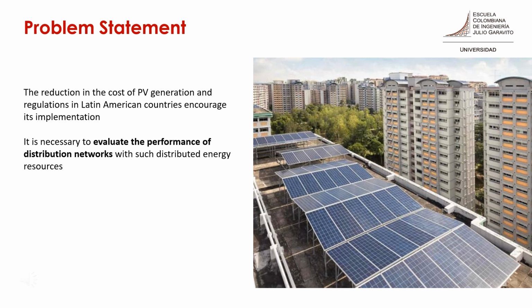Given the stochastic nature of PV generation and the lack of control over its location, the operation of distribution systems becomes more complex. In this way, if the network operator does not have control over the level of penetration or participation, it cannot be certain about the quality of the energy supplied, which is critical for complying with the regulations. For instance, the regulation in Colombia establishes that the voltage cannot vary more than 10% above or below the rated voltage. Thus, to adequately limit the PV penetration level, it is necessary to analyze how much PV generation a distribution network can host without exceeding its operating limits.